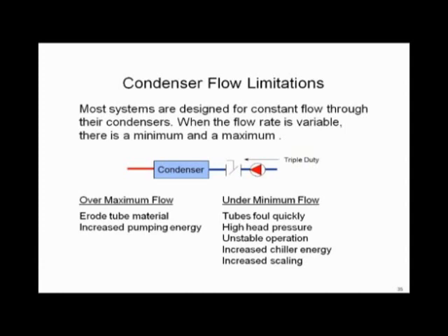On the minimum flow side, most major centrifugal chiller manufacturers today still recommend constant flow through the condensers — it's more efficient and economical. Once you get the chiller running and head pressure under control, they suggest keeping constant flow. If you get the flow rate too low, tubes foul faster, you get higher head pressure, unstable operation, and more scaling on the inside because lower velocity allows rocks and scale to accumulate in the tubes. Efficiency drops and kilowatt draw goes up.